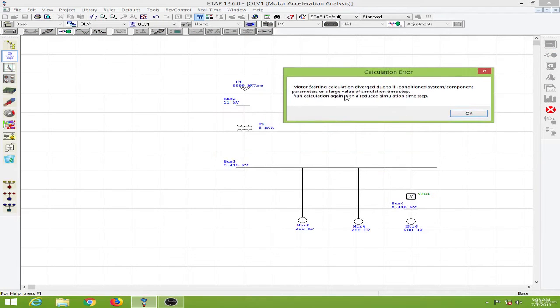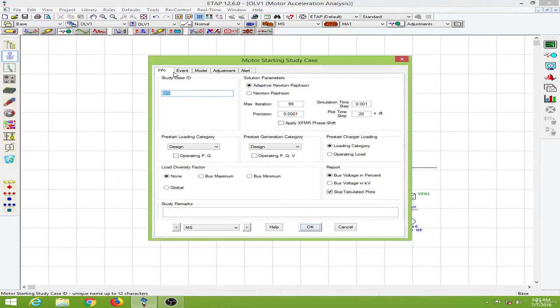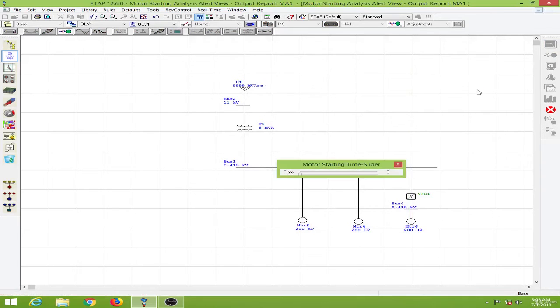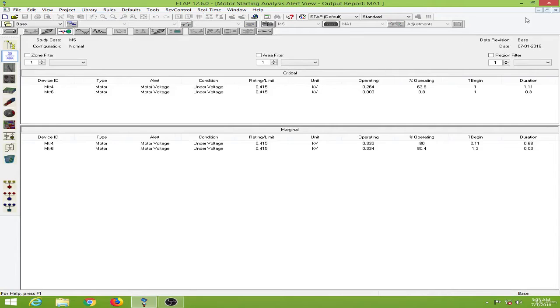It has started to show some errors. We will have to reduce the simulation time step, so we go over here and reduce the simulation time step, click OK, and run again. We will neglect these warnings because this system is drawn only for demonstration purposes. In an actual system we do not start all motors at once. The problem shown is that the motor voltage is becoming under-voltage — motor 4 goes under-voltage for 1.1 seconds and motor 6 for 0.3 seconds.